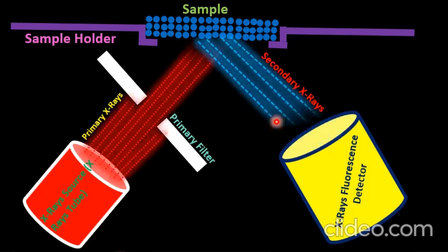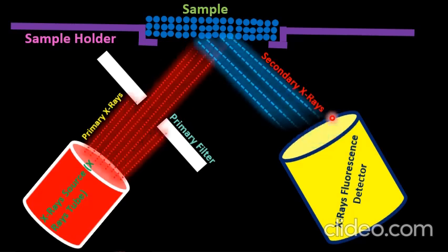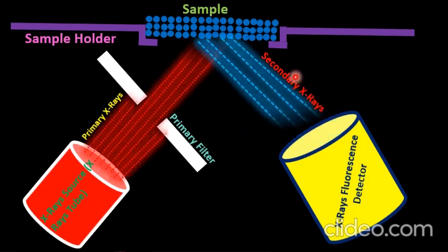In simple terms, XRF spectroscopy is based on the detection of secondary X-rays emitted from a sample surface. Every element emits secondary X-rays with a specific wavelength and energy, and based on that specific energy and wavelength the type of element is identified. The intensity with which secondary X-rays are generated gives information about the chemical composition — the percentage of each element present in the material.